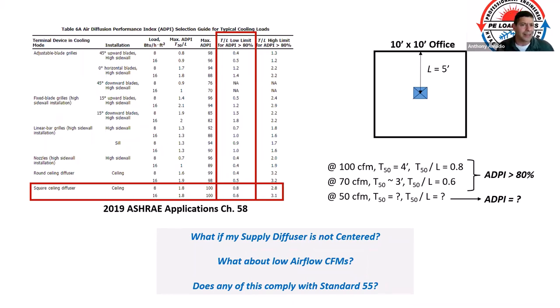You'd have to know what the building load per square foot is, for cooling and for heating. Older tables didn't have things for heating, but the newer tables do. They'd say, look, if you know your throw — this would come from the manufacturer table based on that CFM — if you were in this range, you would have an acceptable ADPI. You should have thermal comfort.